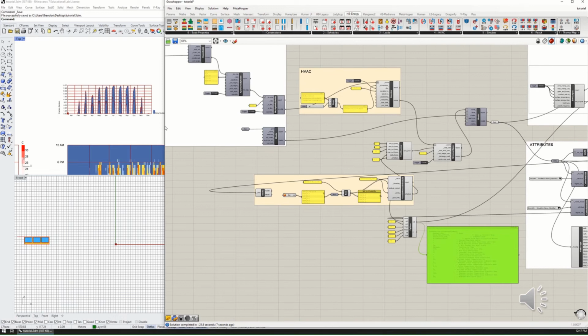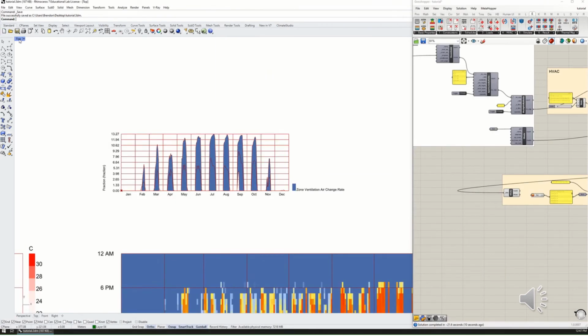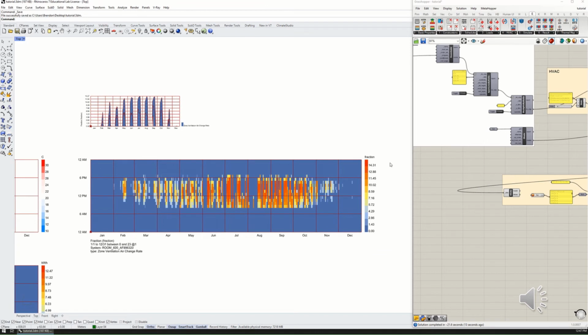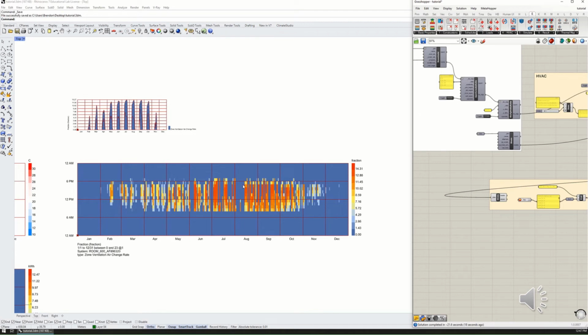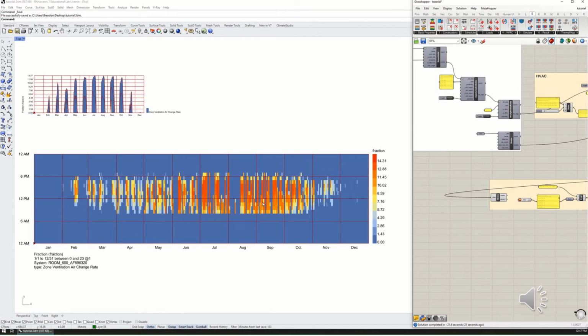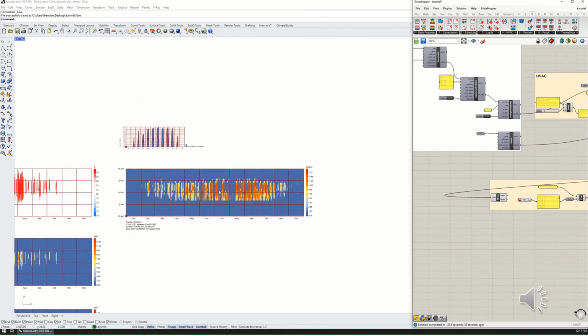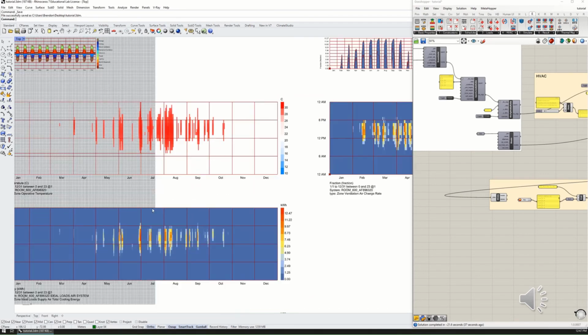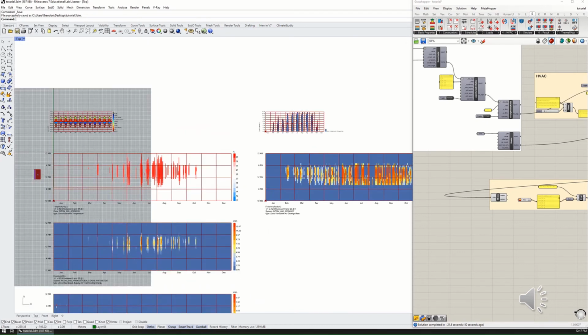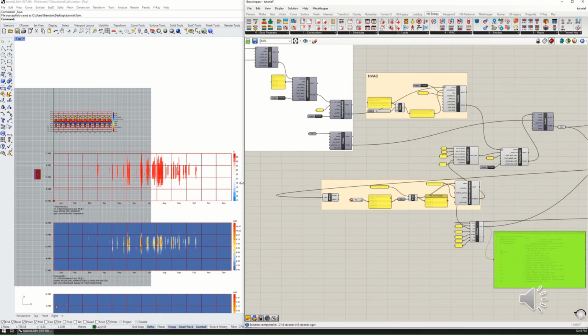Yeah, so what we're seeing now is that we've got about 14 air changes per hour, with that's our 10 air changes per hour that we added as supplementary ventilation fan-based cooling, and then another 4 or so air changes per hour that the economizer is providing within the ideal load system. So these are additive measures. It's not one replacing the other. And then we're getting associated reductions to the cooling because of the added fan.